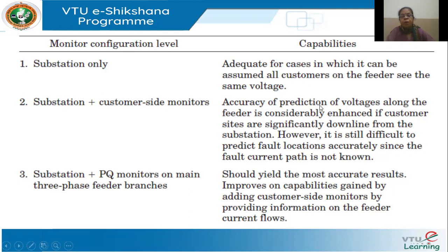So the accuracy of prediction of voltages along the feeder is improved if the customer sites are significantly downline from the substation. That means they're at the end, radially at the end. However, it is still difficult to predict the fault location accurately since the fault current path is not known. I don't know which path the current will take because I'm not monitoring the current through the feeder. So exact location of the fault is not possible.